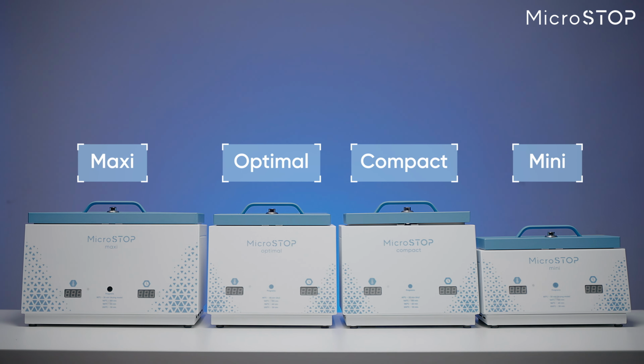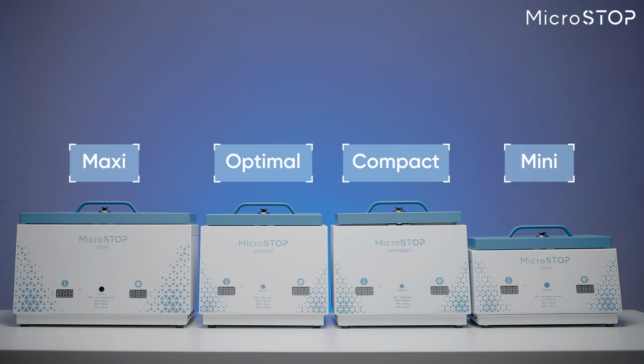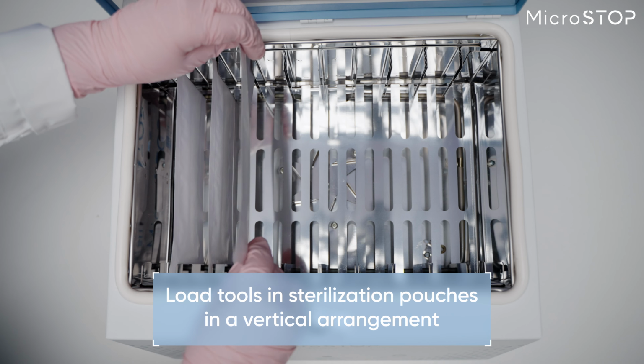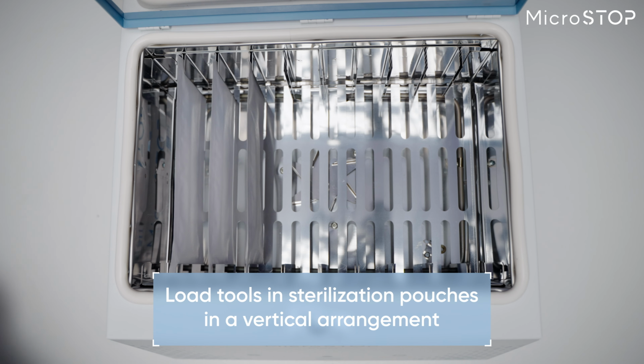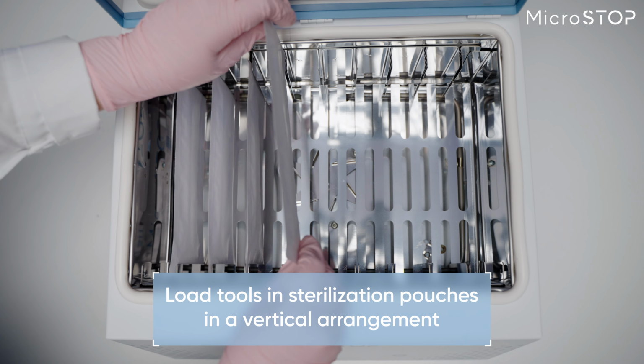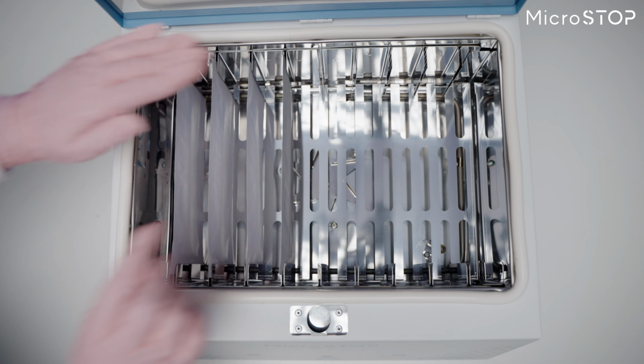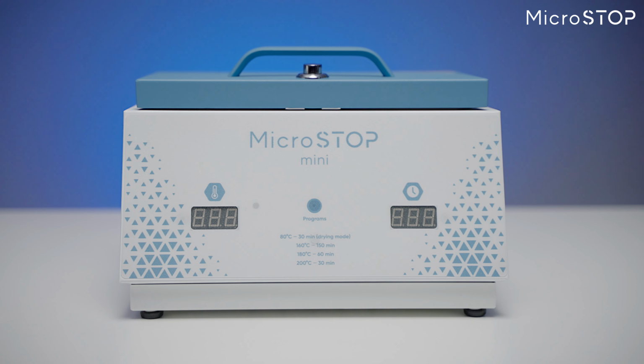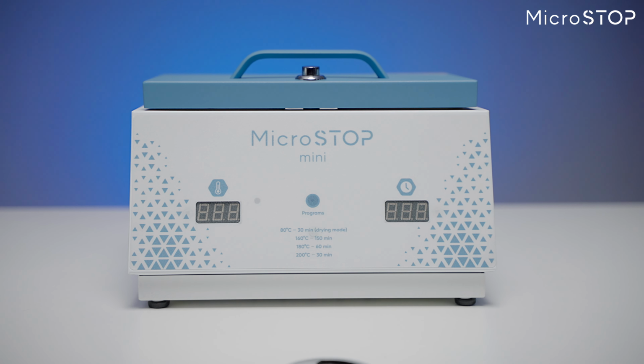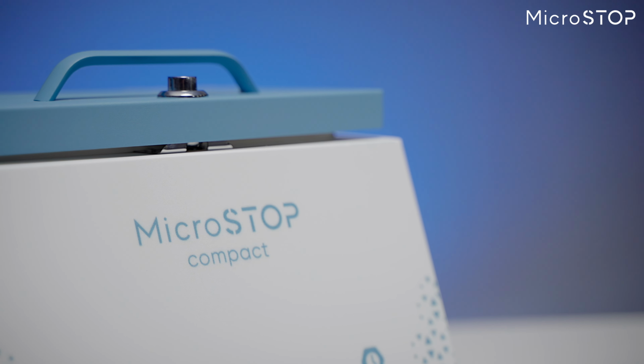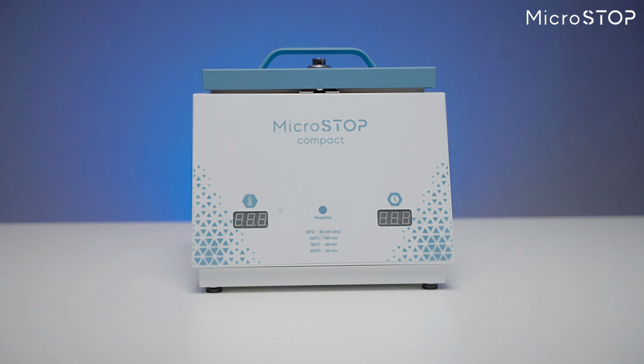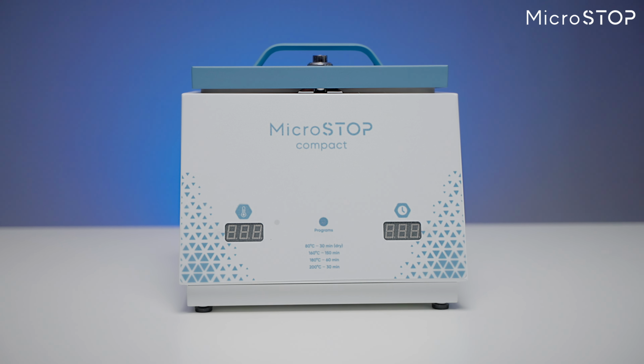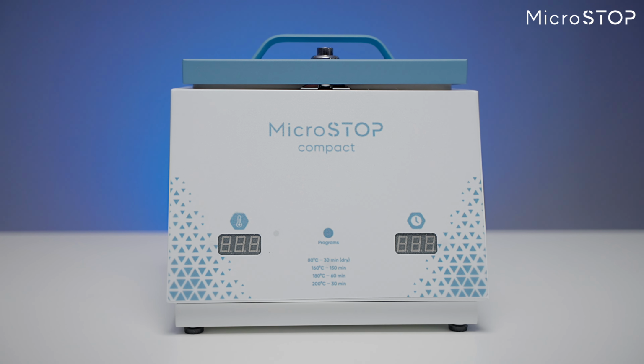A common and special feature of the Microstop Mini, Compact, Optimal, and Maxi models is the possibility to load tools in sterilization pouches in a vertical arrangement. This type of tool placement is a unique development of Microstop, which allows for rational use of the chamber space and makes the device compact. Therefore, you will always find a place for this type of sterilizer even in the smallest of rooms.